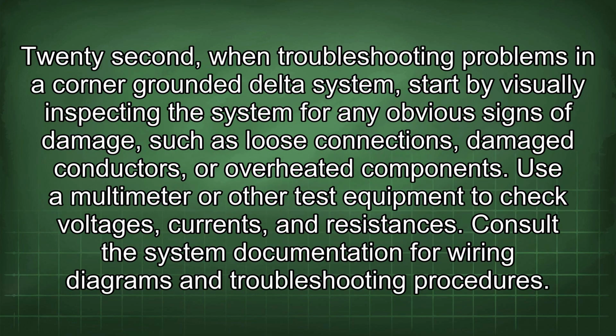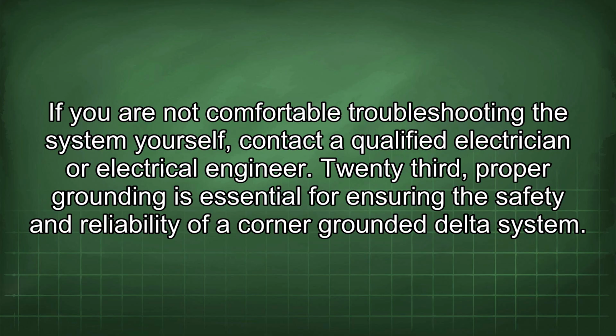22nd, when troubleshooting problems in a corner-grounded delta system, start by visually inspecting the system for any obvious signs of damage such as loose connections, damaged conductors, or overheated components. Use a multimeter or other test equipment to check voltages, currents, and resistances. Consult the system documentation for wiring diagrams and troubleshooting procedures. If you are not comfortable troubleshooting the system yourself, contact a qualified electrician or electrical engineer.